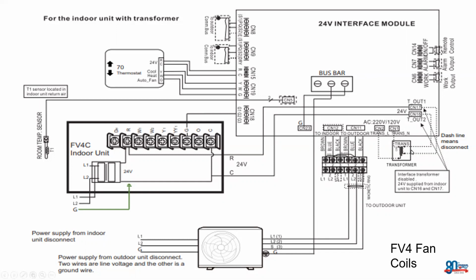Okay. One other thing to note on here as well is that the factory-installed transformer that steps down our incoming power to 24 volts AC can be removed. All you have to do is unplug it right on the power lines, and then also, of course, the secondary side of the transformer. We're just going to go ahead and remove that. Guys usually ask, what are we supposed to do with it? I always tell guys just to keep it in case you ever need one. If you don't need it, you can always dispose of it as well.